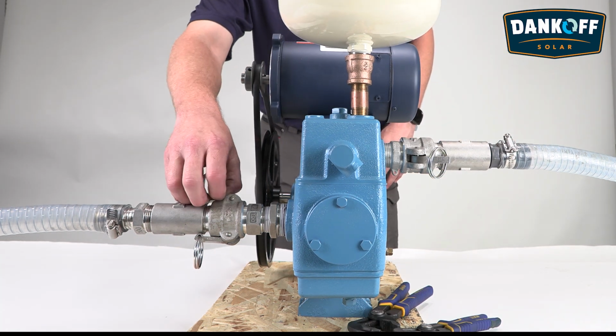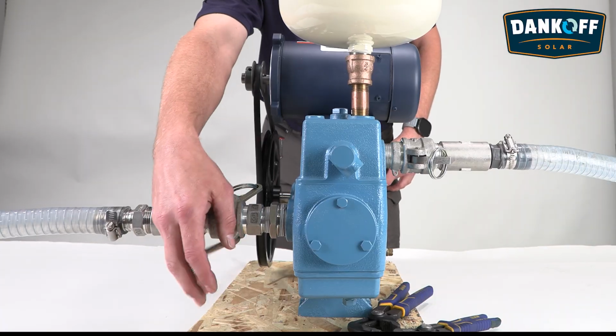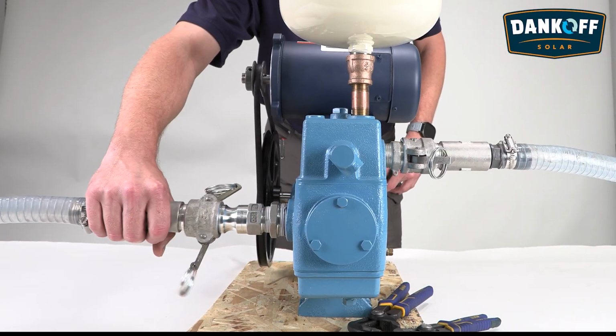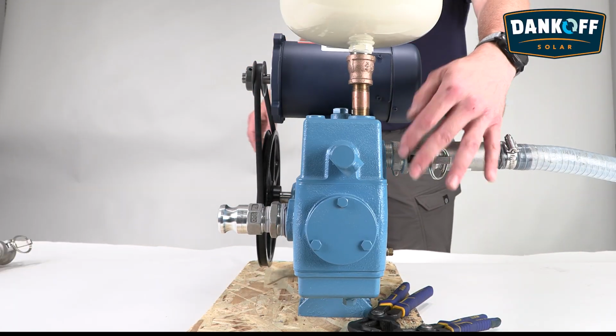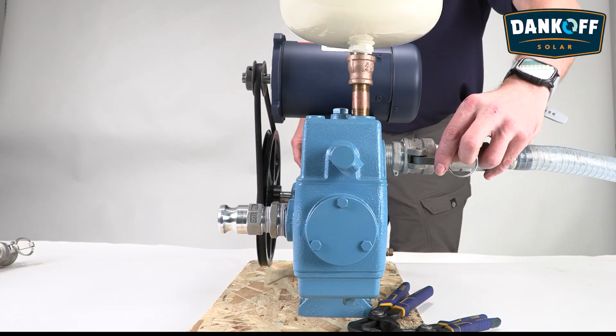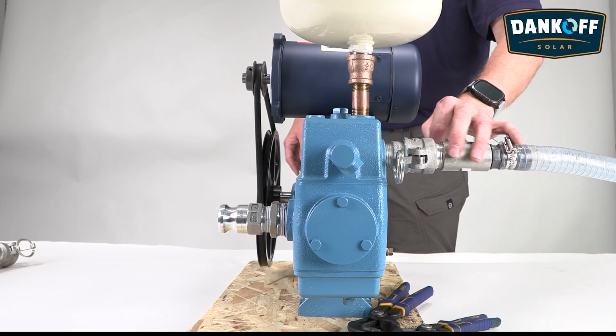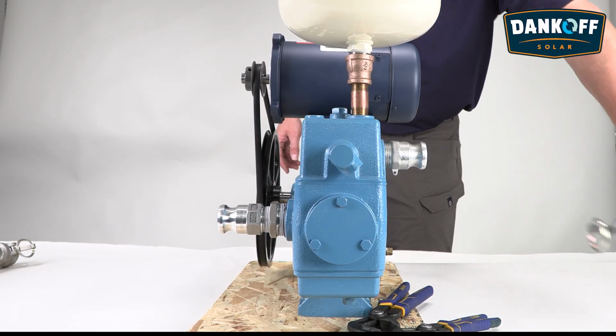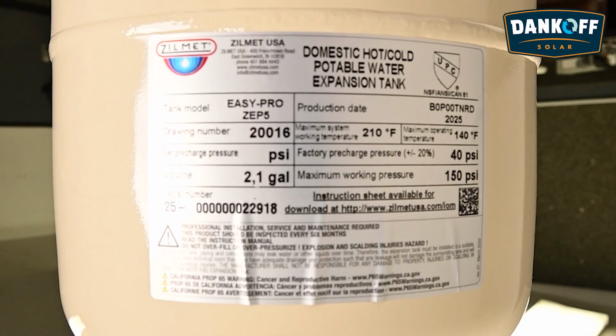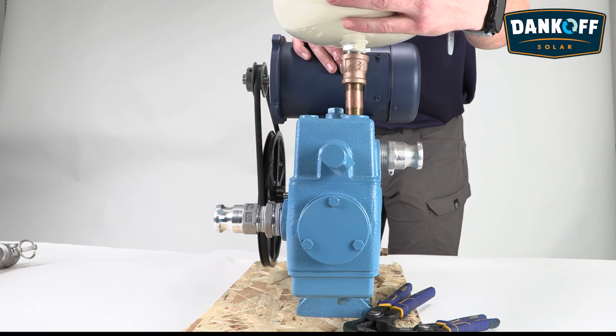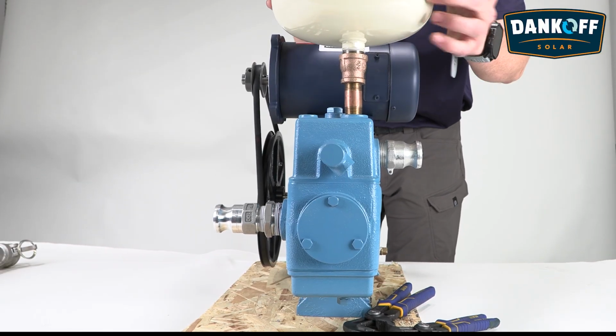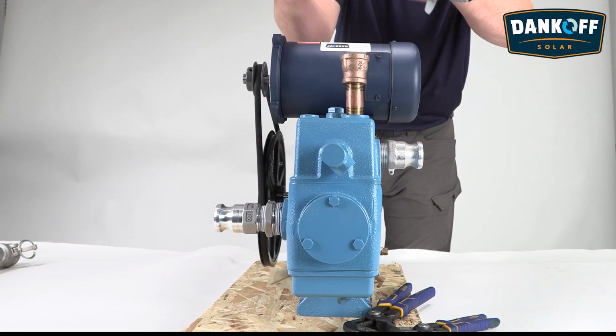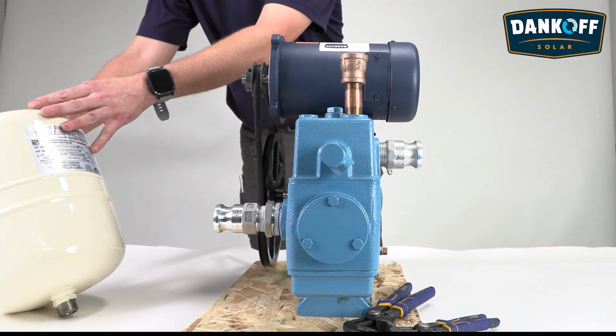The first step would be removing the intake line from the pump head. Go ahead and make sure that drains out. Next, we would remove the discharge line from the pump head, draining as well. After that, we would remove the expansion tank. We would remove this to relieve any vacuum that's in the pump and set this aside. Ensure this drains out if there's still any water in it.